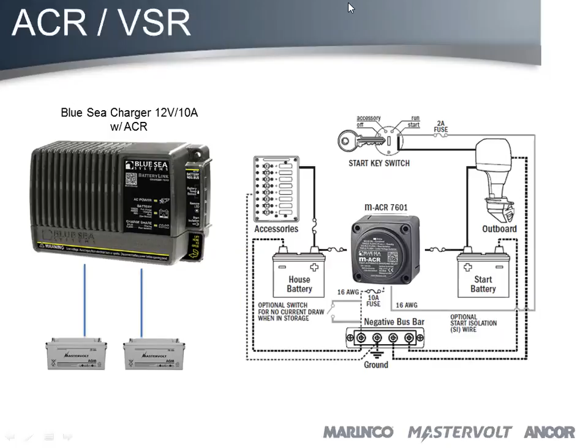What about when the generator is trying to charge the battery and the alternator too, does it matter? As soon as the battery charger gets AC power on the input side, it will leave that contactor open, so it will not take power from the alternator. Well, it will take power from the alternator, but only for that particular battery, which actually helps, because the current on the charger will then primarily go to the second battery, so you get a faster charge. Good question.